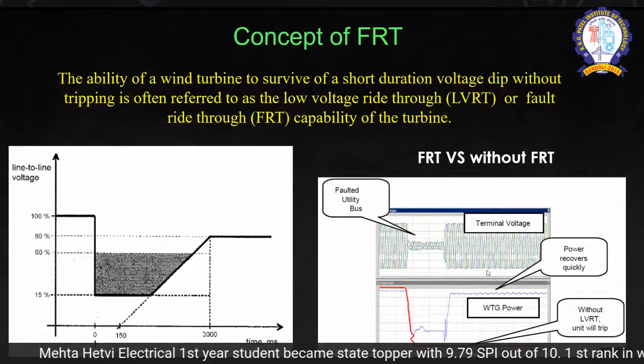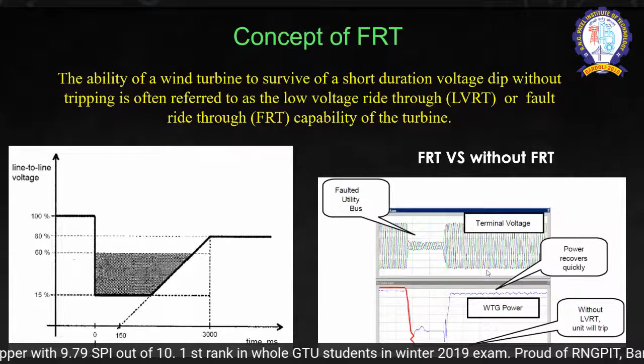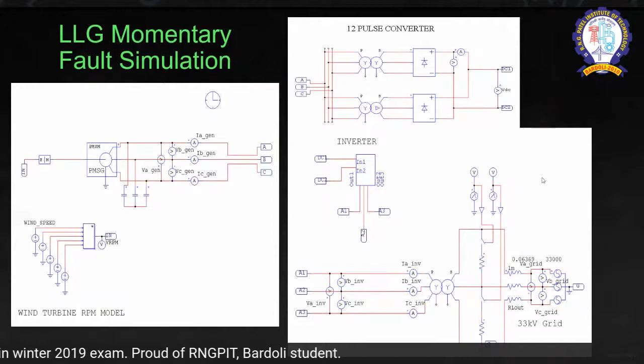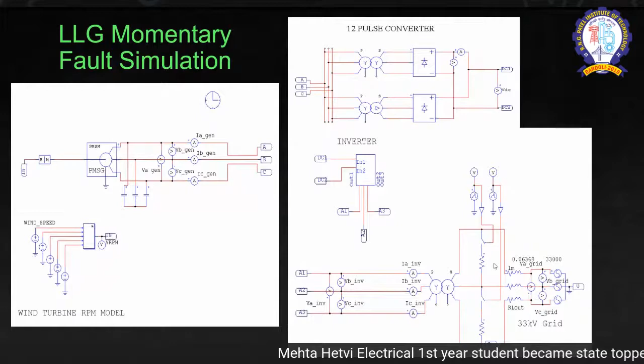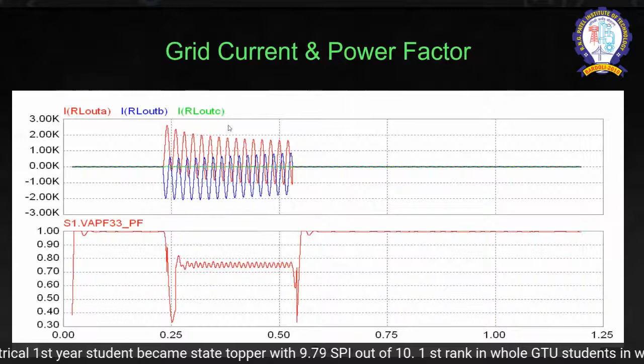This is the common example of the comparison. Without the LVRT option, it might trip, and with the LVRT option, it might survive, and the power will recover quickly. With the incorporation of FACTS devices, they will provide some power in this duration, so the wind turbine is tightly connected with the utility or grid. So now in this case, if there is a double LG fault over here from the grid side, line to line fault and line to ground fault, then this is the increment in the grid current and decrement in the power factor. This effect is known as FRT.